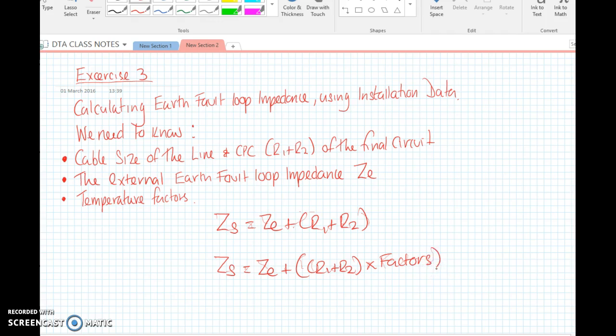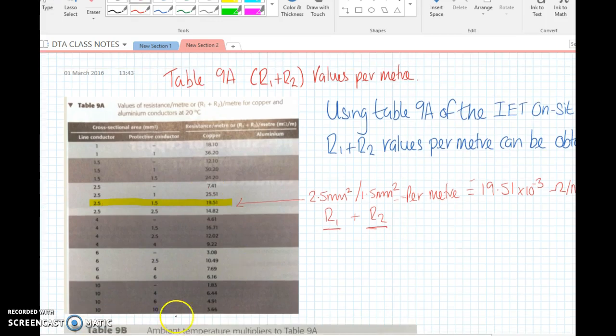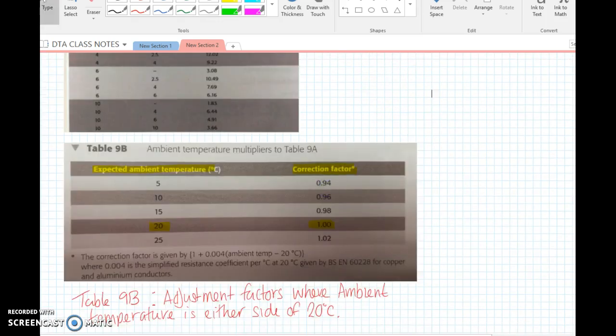This is table 9a of the on-site guide. On this left column we have our line conductor R1, so a 1mm on its own per meter is 18.1 milliohms per meter. Then we have a protective conductor, so we've got R1 and R2, going all the way down to 50mm.